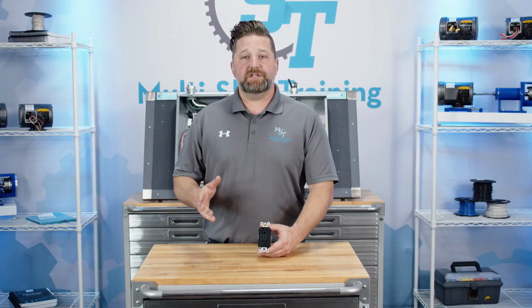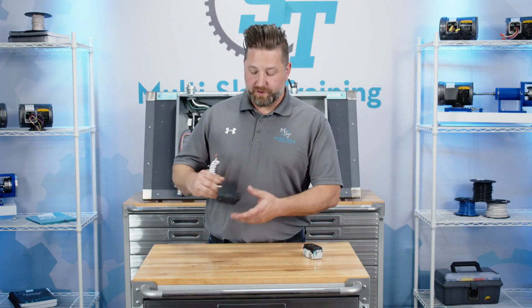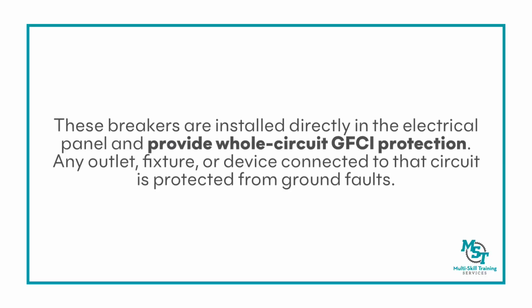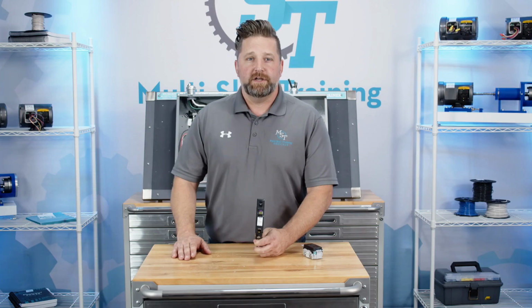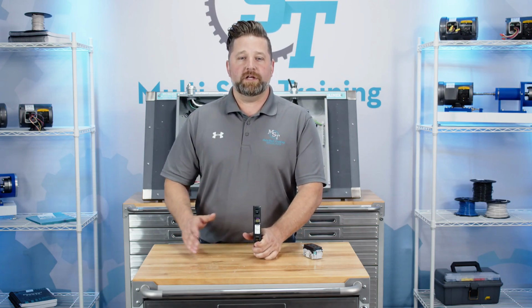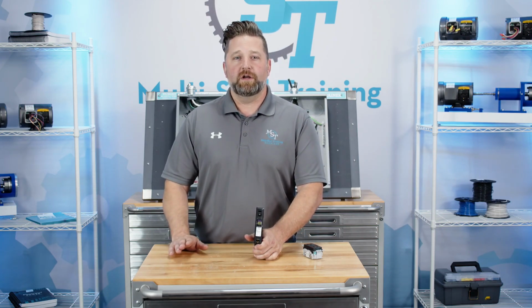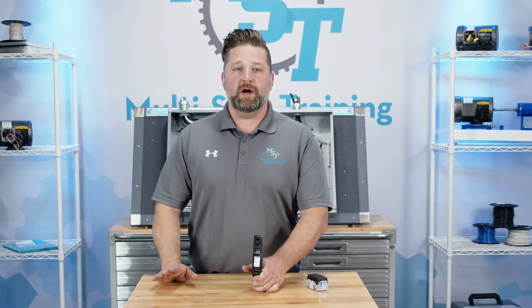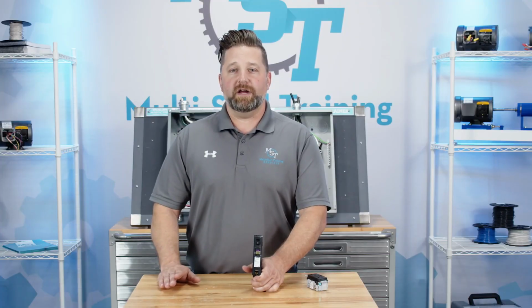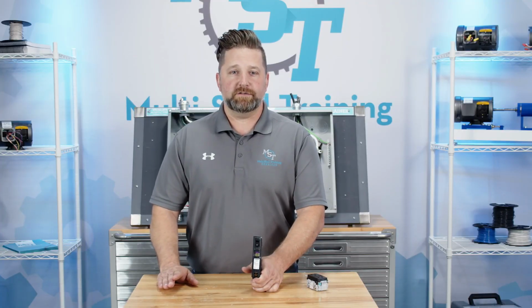In addition to GFCI receptacles, GFCI circuit breakers are also available. These breakers are installed directly in the electrical panel and provide whole circuit GFCI protection. Any outlet, fixture, or device connected to that circuit is protected from ground faults. GFCI breakers combine the overload and short circuit protection of a standard breaker with the ground fault protection of a GFCI. This is a useful option with multiple outlets or devices on a single circuit needing GFCI protection, especially in garages, basements, and outdoor circuits.